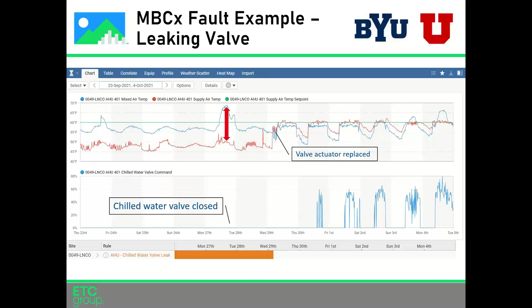So much better control. This is a really good example of a fault that you would never really be able to see from somebody getting uncomfortable, because that cold air is going to go in and just get reheated. And most likely your occupants are going to feel just the same whether or not this is happening. So this is an example of where the software can bring to light these inefficiencies that are hiding in the system.